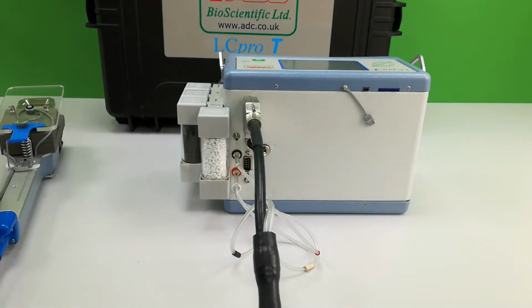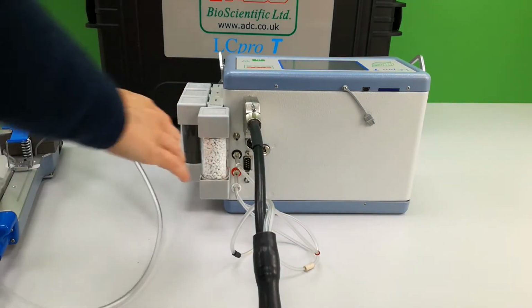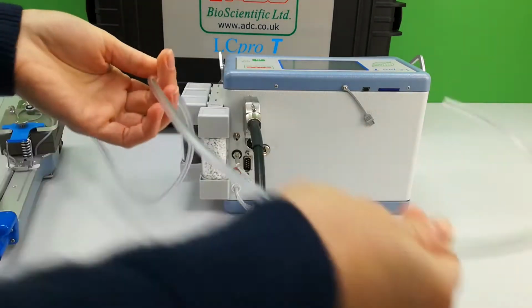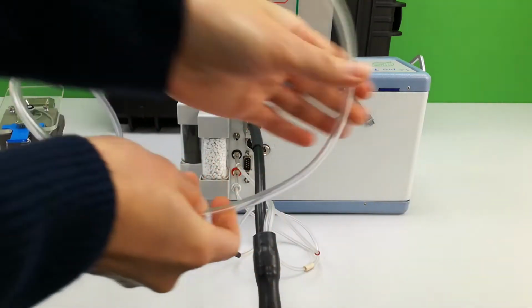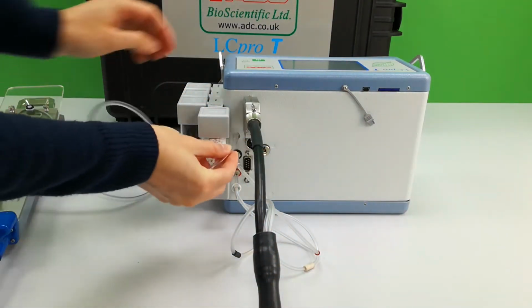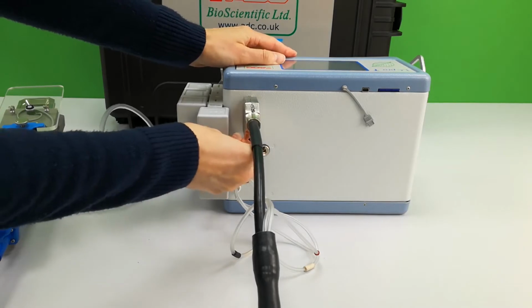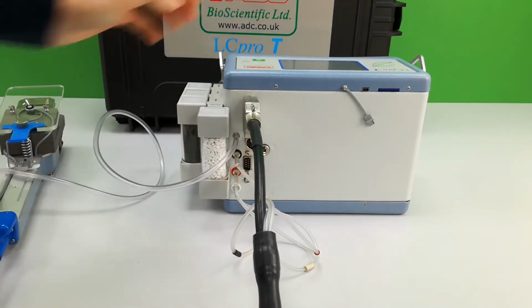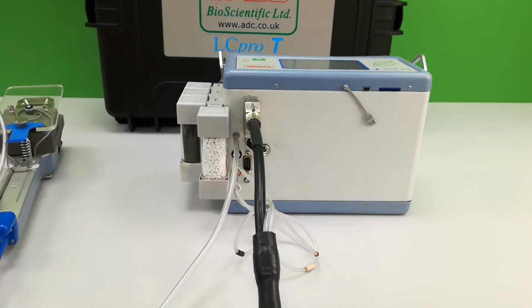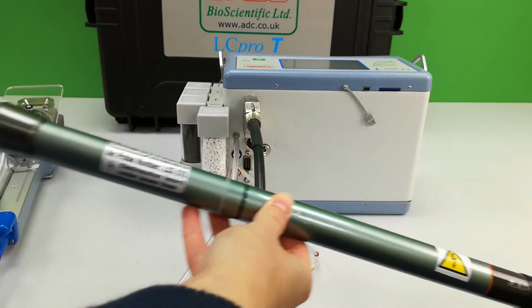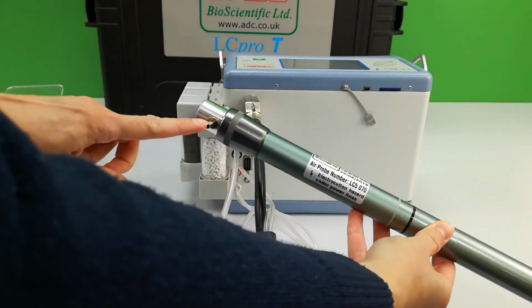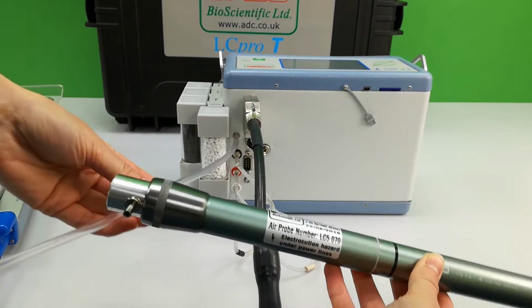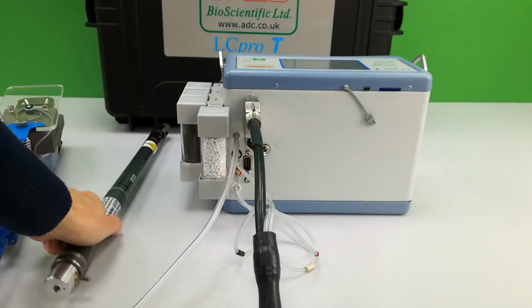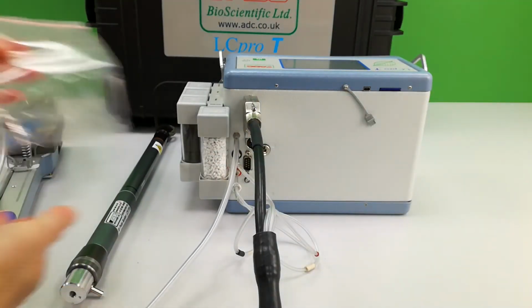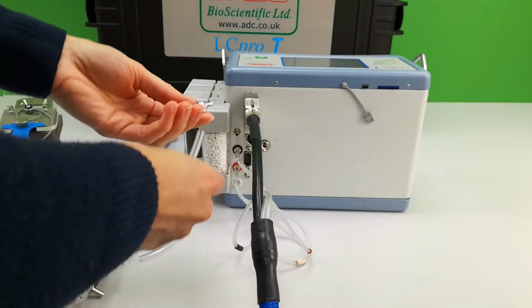When setting up LCpro T for the first time, attach the length of tubing supplied and hang the other end out of a window away from sources of CO2 such as your own breath. When working outdoors, use the air probe supplied in the carry case. Attach the length of PVC tubing supplied in the spares kit to the inlet near the base of the probe.